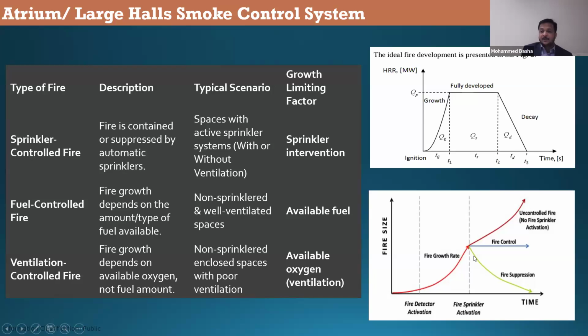In your smoke management calculations, sometimes you need to consider a fuel controlled fire. Sometimes you need to consider a sprinkler controlled fire. We will see when we should use these terminologies when we are designing the smoke management system. Ventilation controlled fire, the third, is not relevant to the smoke management system, but let us see. Fire growth depends on available oxygen, not fuel amount.